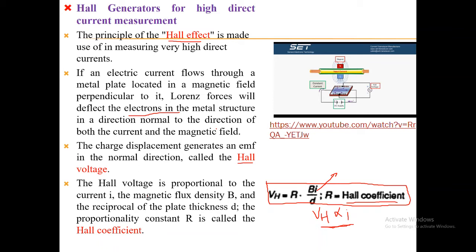Now let's see Hall effect current transducer types. By using Hall effect principle to build current transducer, here come two types of current transducers. The first type is open loop Hall effect current transducer. When primary current goes through the conductor, it will generate magnetic field around the conductor. If we put the conductor through the center of a magnetic core to concentrate the field, and place a Hall element in the gap of the core, we will get the Hall voltage. Let the Hall voltage pass an amplifier to become an easy read value.